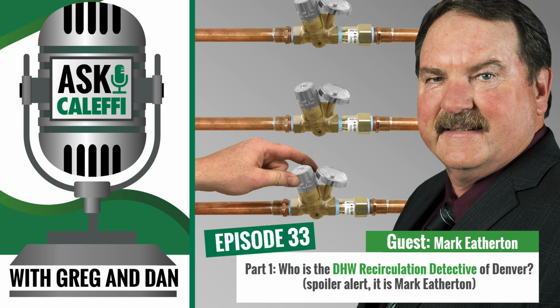So you've got to look at the system as a whole. You've got to record the nature of the complaint. And the complaints that you hear in the field are going to vary all over the place. You've got to stop and think about what it is that they're saying, when it occurred, where it occurred, and were there any similar occurrences within that same particular riser stack. And if there is, you start at the top and work your way down until you get to the floor that doesn't have the problem, and believe it or not, you've discovered the problem. That's where the problem is.